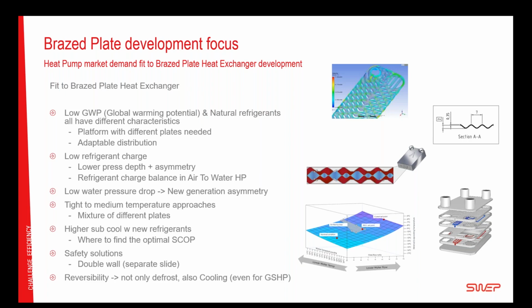We're also focusing on low refrigerant charge, and we've worked a lot with the asymmetry and the press depth needed to manage this, especially with the mildly and highly flammable refrigerants used today. Low refrigerant charge has become more of interest, but we also need to understand it has to be balanced, especially for air sourced heat pumps—balanced against the air coil. So we also have a broader platform so that for each situation we have different heat exchangers to choose from.